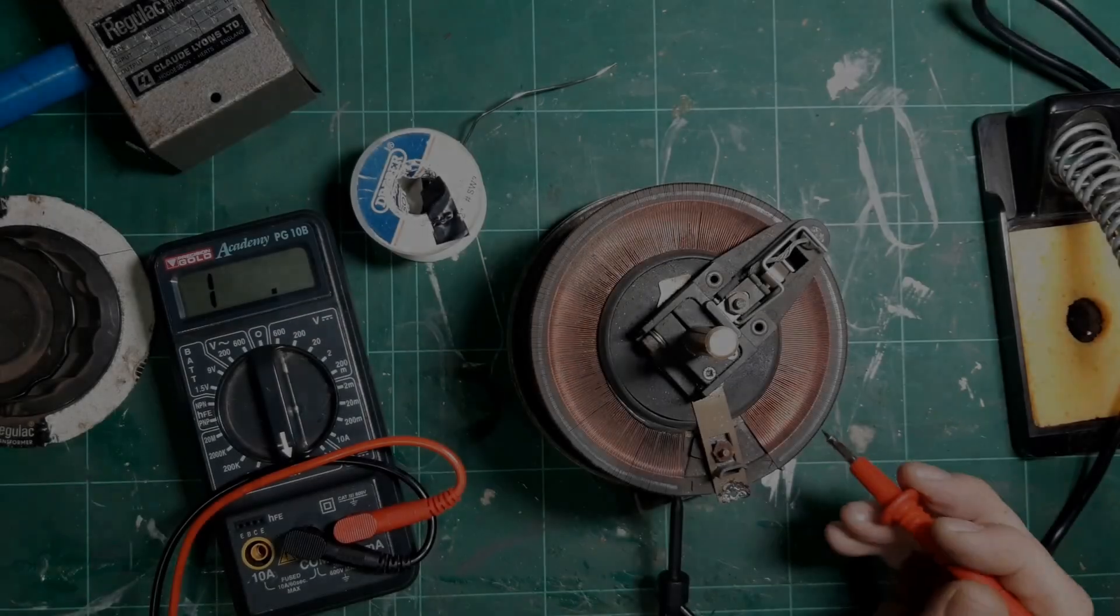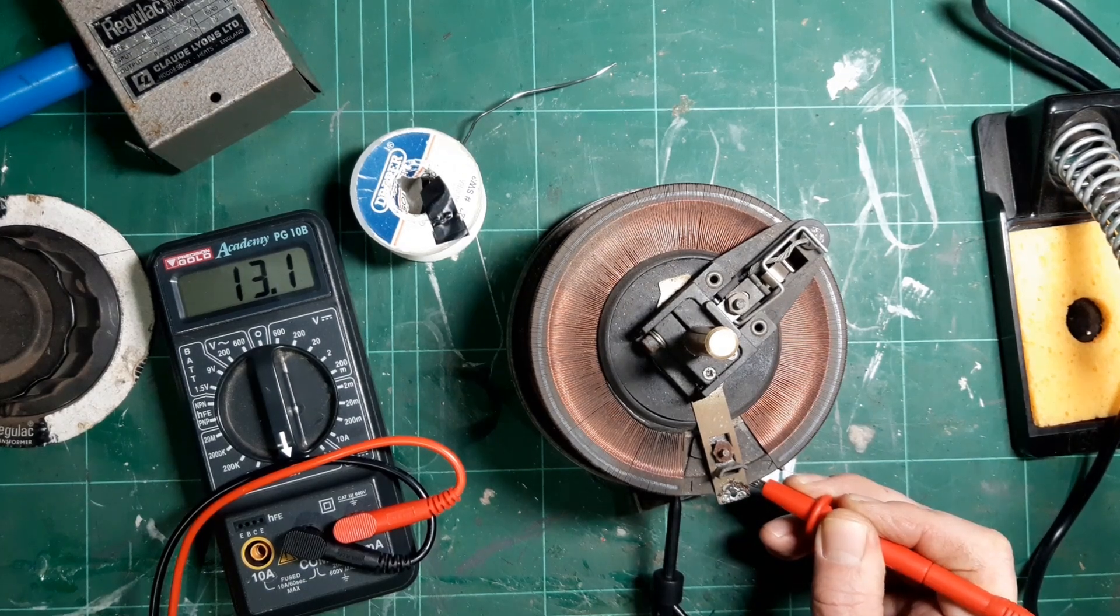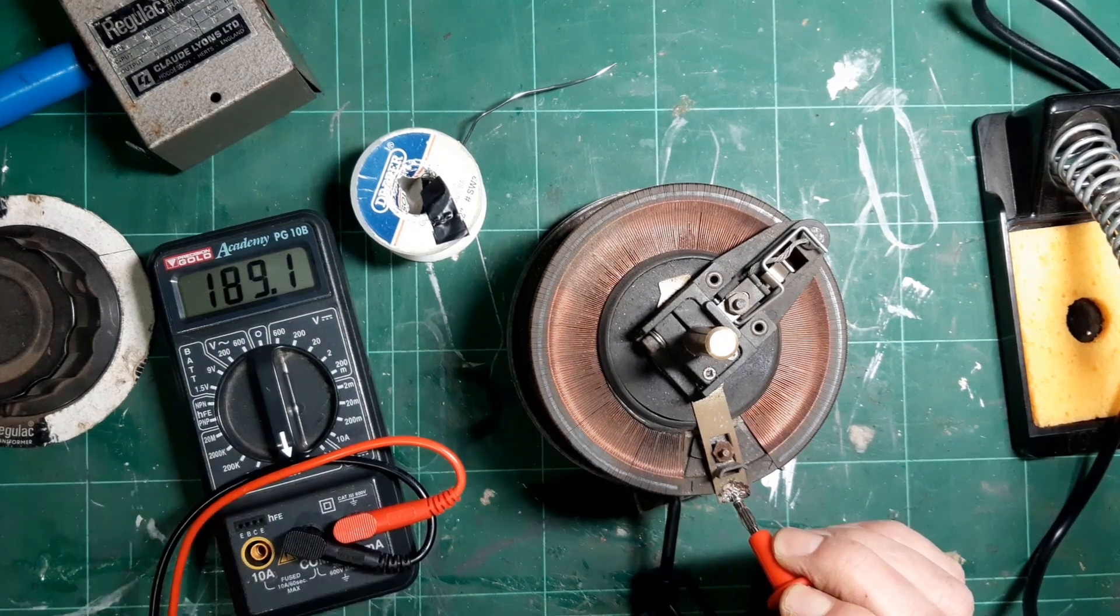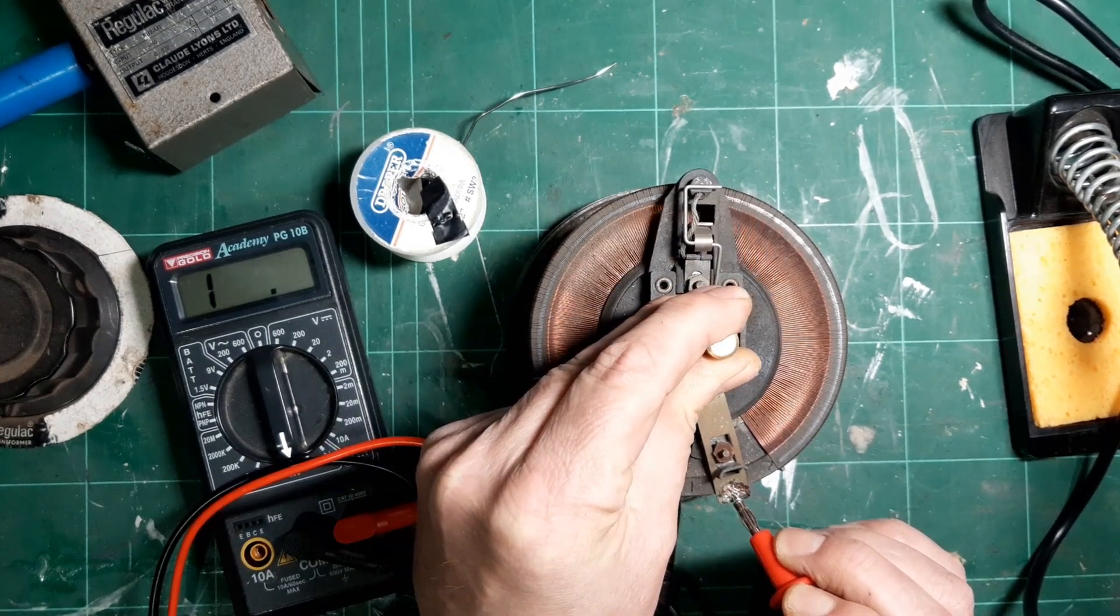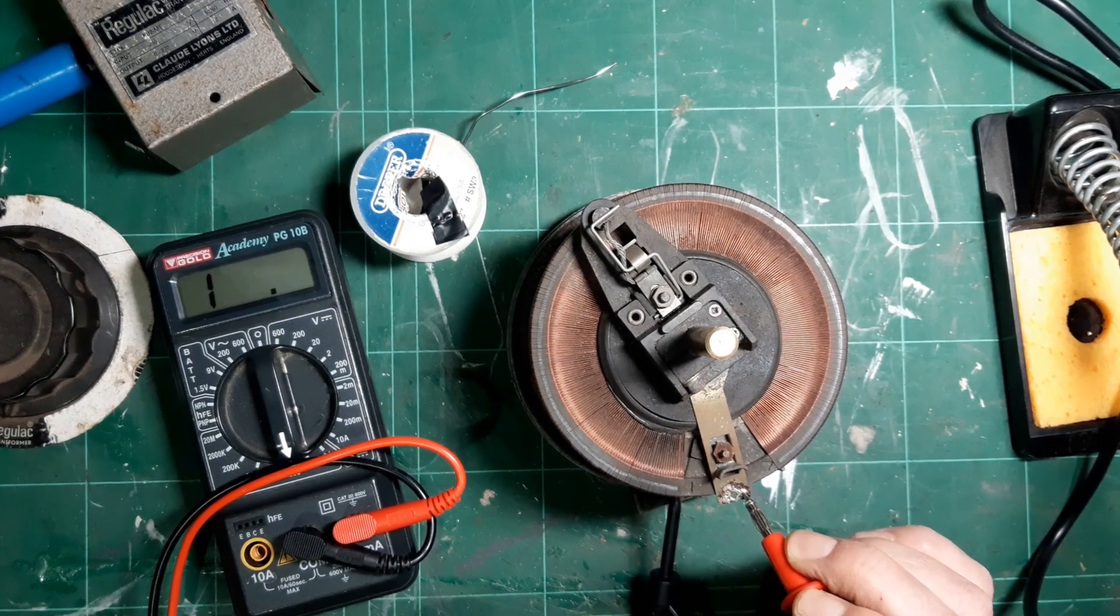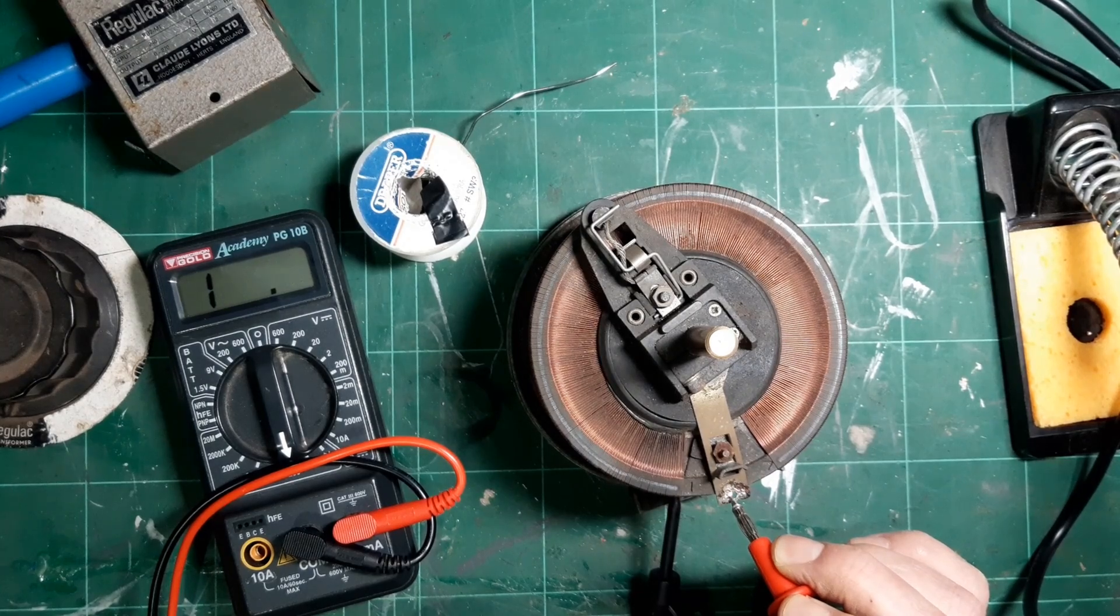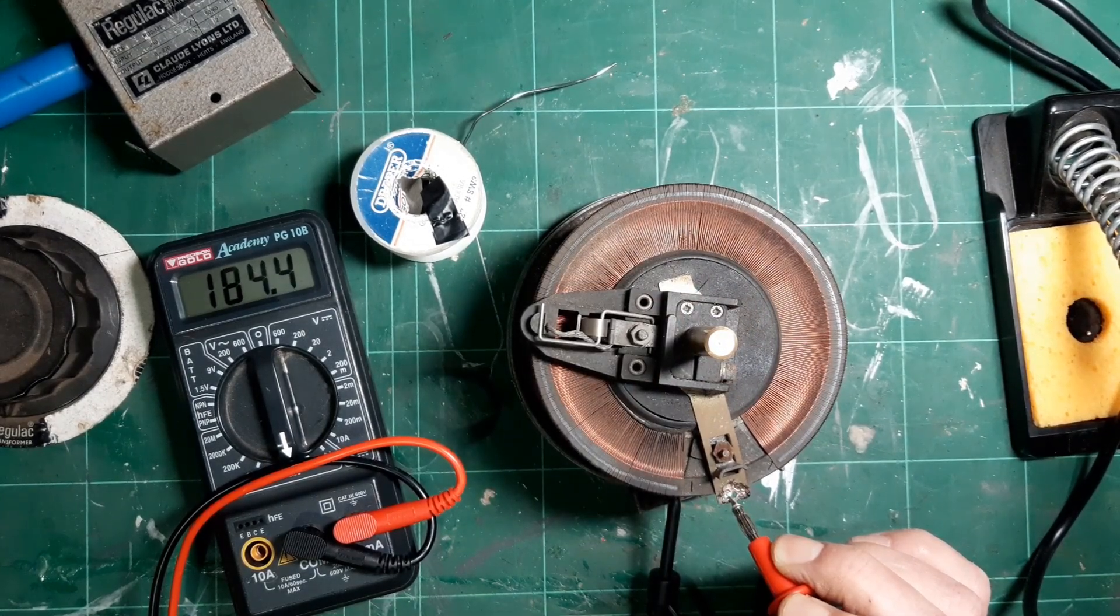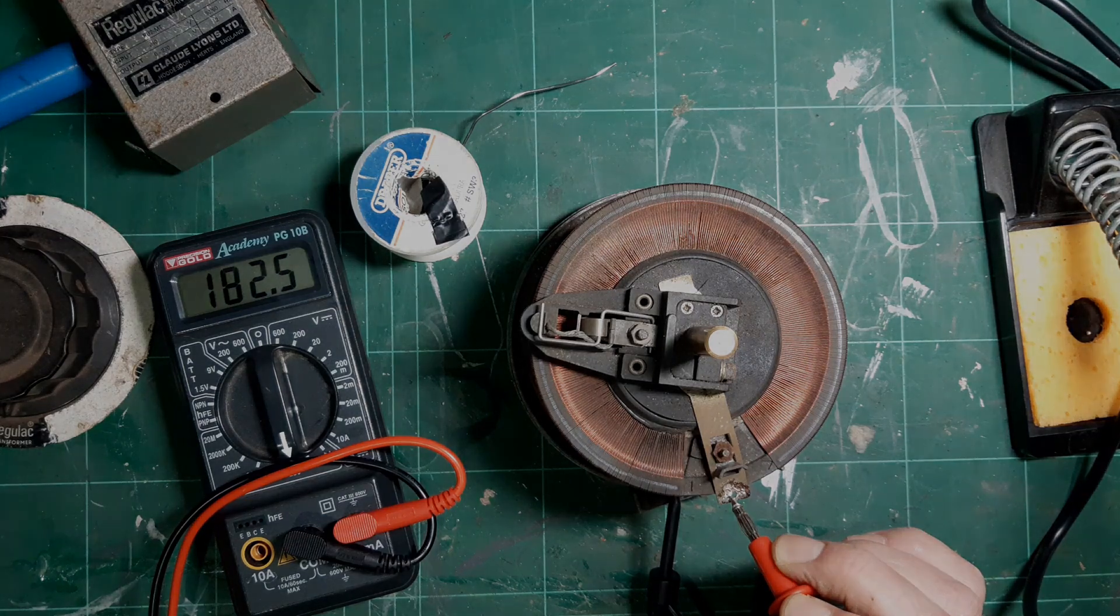I just want to do a continuity check, really. Let me just put the probe on. So I'm getting some resistance there, so it's not a dead short and it's certainly not open circuit. I'll just put it on this part as well. I'm getting resistance—it's a lot higher resistance, I'm curious about that, probably because there's lots of machinery in the path there. That indicates to me that probably needs to be cleaned up. I'm really just measuring the resistance there. Yeah, definitely getting something, so I think basically electrically it's there. I think it's purely a case of just cleaning up, which I'm going to get on with now.